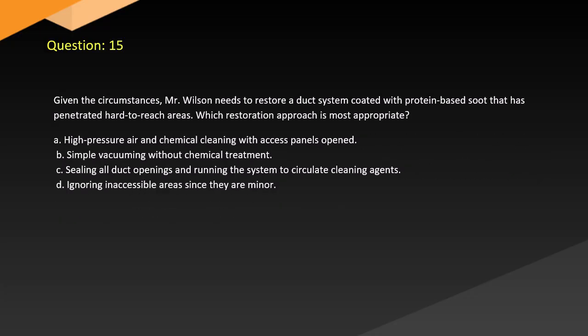Question 15. Given the circumstances, Mr. Wilson needs to restore the duct system coated with protein-based soot that has penetrated hard-to-reach areas. Which restoration approach is most appropriate? A. High-pressure air and chemical cleaning with access panels opened. B. Simple vacuuming without chemical treatment. C. Sealing all duct openings and running the system to circulate cleaning agents. D. Ignoring inaccessible areas since they are minor.